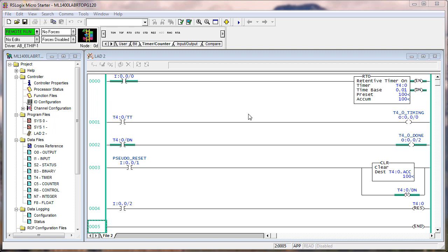And by the way, you can use the reset instruction for any timer instance of a timer data type, whether it's being instructed by a TON, TOF, or RTO. A timer data type is a timer data type. The reset instruction doesn't know what kind of instruction was addressing that timer data type. It just clears it.